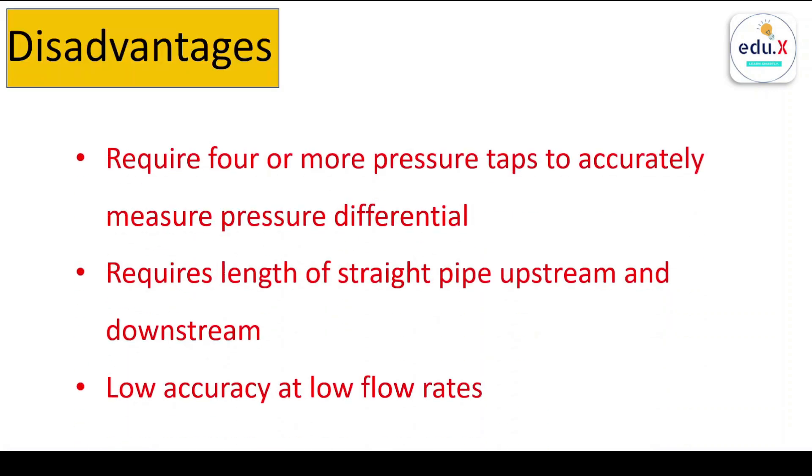So let's look at the disadvantages. They require four or more pressure taps to accurately measure the pressure difference, and also they require certain lengths of straight pipe to the upstream and downstream. So it means they require higher space to install for flow measuring purposes. And also they offer low fluid measuring or flow measuring accuracy at low flow rates.